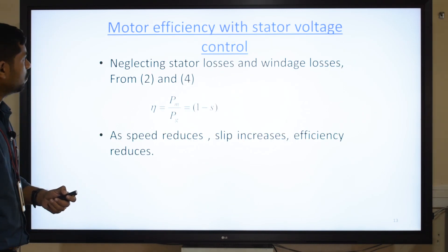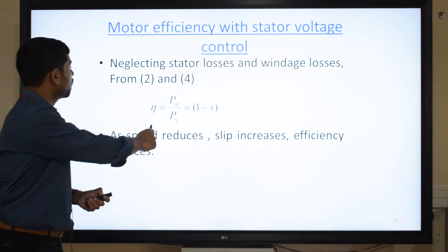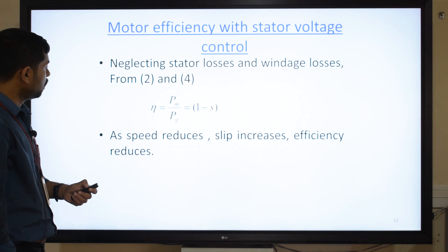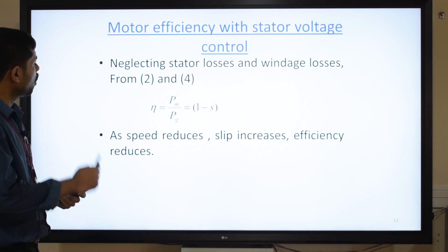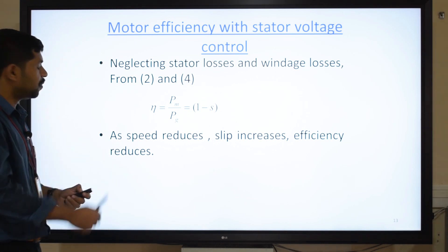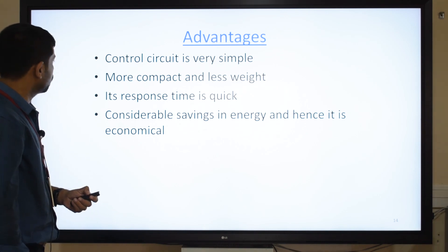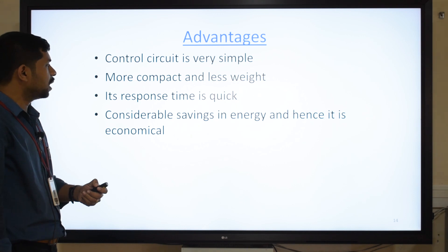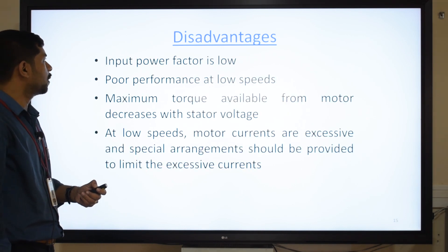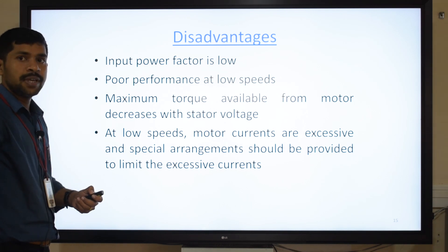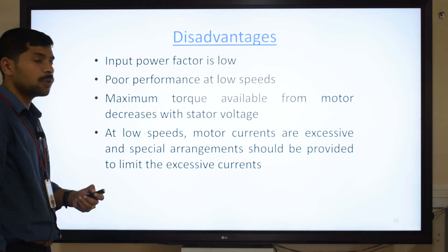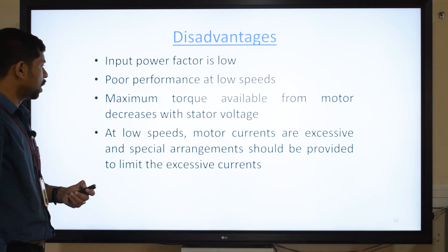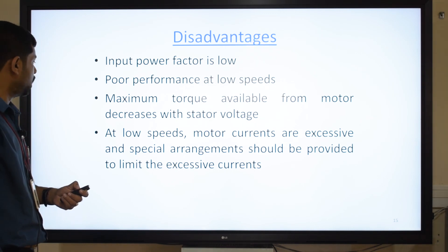The efficiency equation, derived from equations 2 and 4 by neglecting stator losses and windage losses, is: efficiency equals (1 minus s). So whenever speed reduces, slip increases, and whenever slip increases, efficiency is reduced. Advantages: the control circuit is simple, compact, and lightweight; response time is quick; and there is considerable energy saving, making it economical. Disadvantages: input power factor is very low; poor performance at lower speeds; maximum torque available decreases with stator voltage; and at low speeds, motor currents are excessive, requiring special arrangements to limit them.